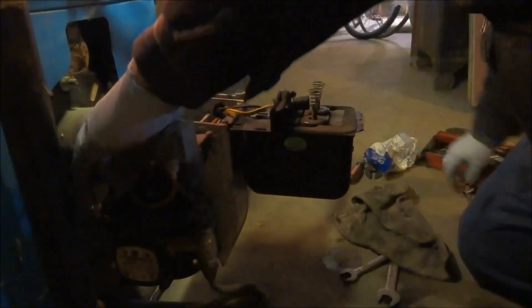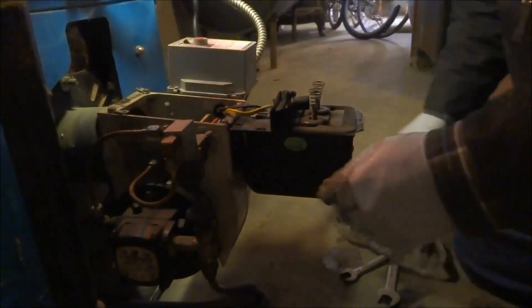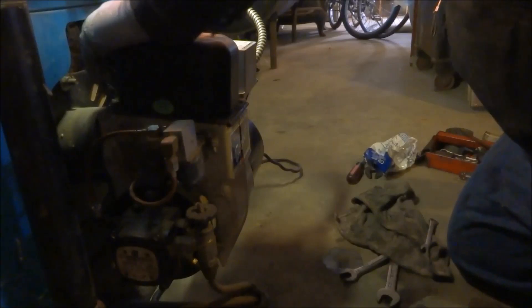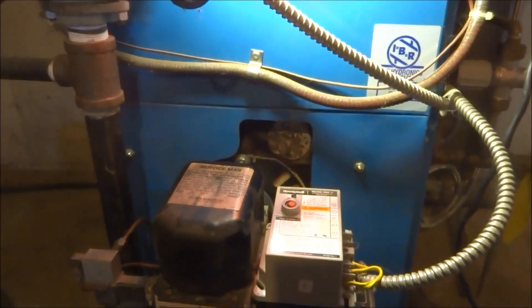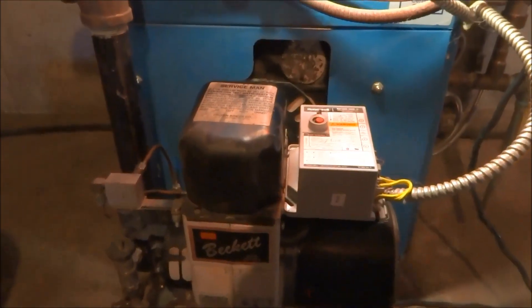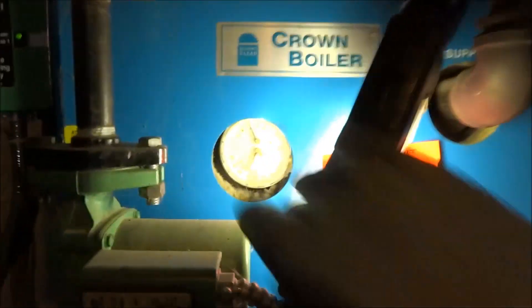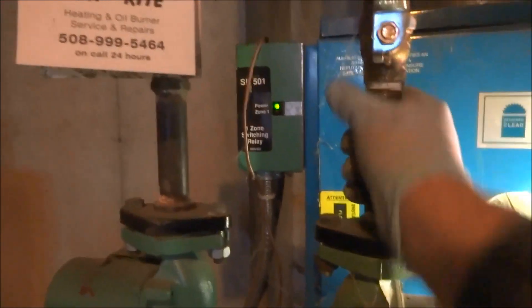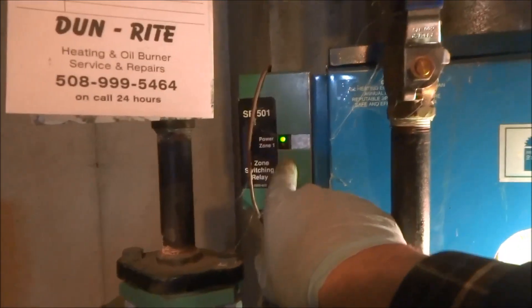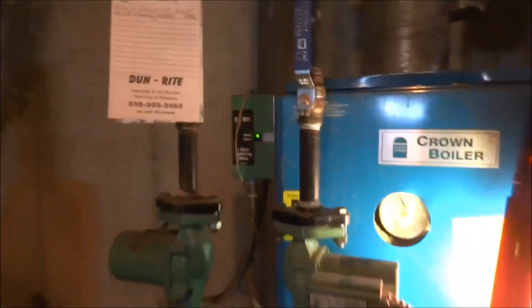This guy's done without heat all night, so I'm going to get it back up and running for him. Hopefully these zones aren't frozen upstairs, we'll find out. There we go. It's going to get up to the low limit, which is 160 for the circulators kick in. He's got one zones not calling here, plus he's got them off. Like I said, he's got a pellet stove.